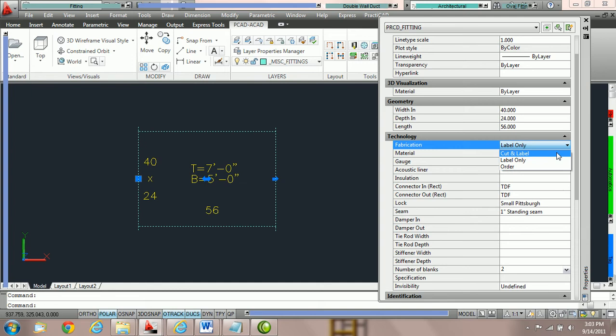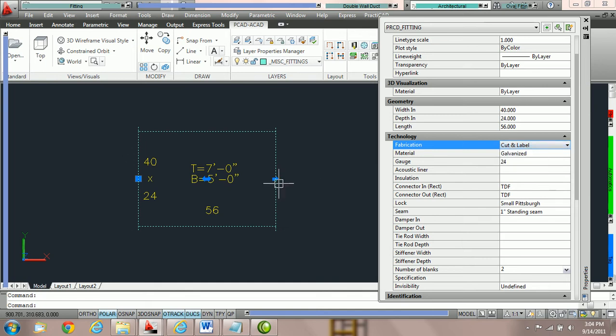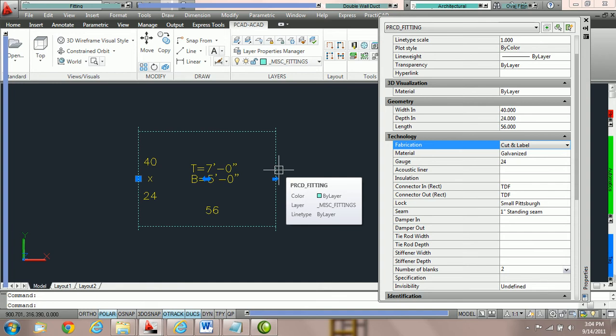The first — cut and label — basically means that this duct is going to go to the plasma cutter. Therefore it's not going to follow any standard set of rules for finished length with a coil line, which is what label only is for. It simply means that whatever properties you put in, PractiCAD is going to accept them.